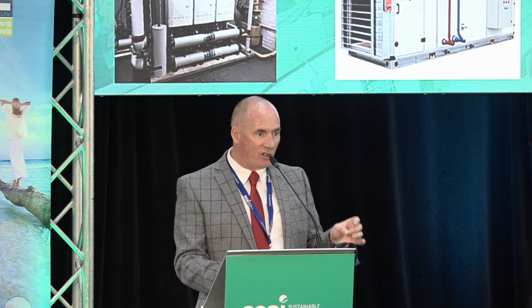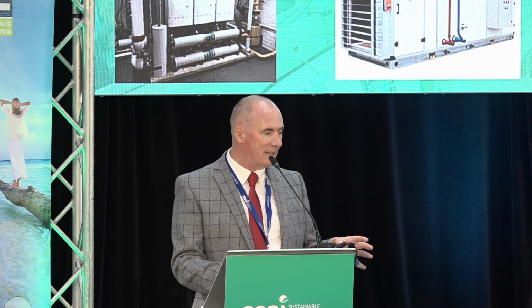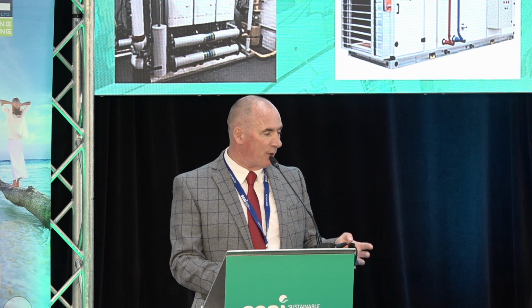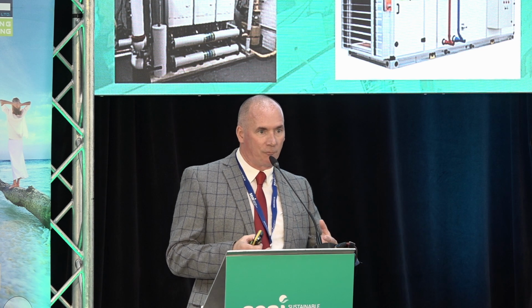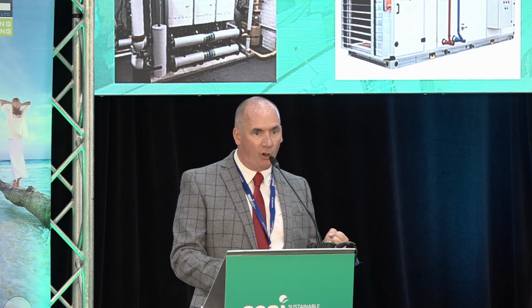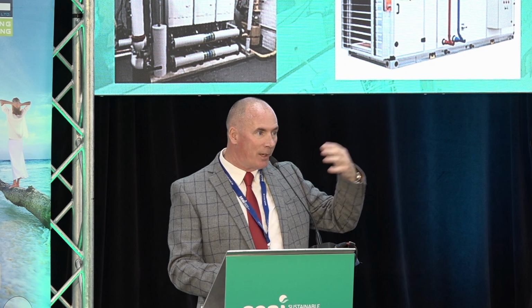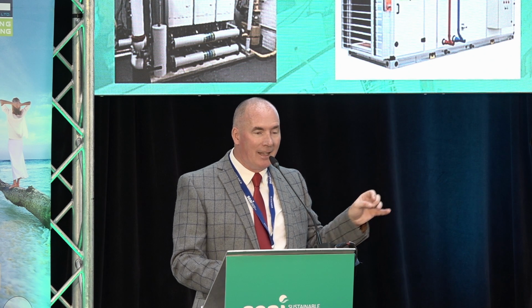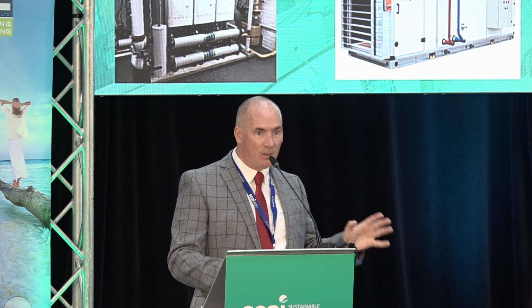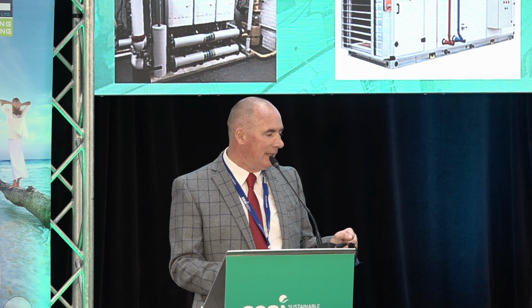So the historical alternative was a water-based system. You would typically have a chiller, a water chiller that provides the cooling, and you would have had a boiler that satisfied the heating. The problem with this, anybody that knows refrigeration and chillers will know that the condenser is basically dumping energy. As we're cooling the water, we're taking energy from it and we're dumping that from the condenser to the environment. And at the exact same time, we could have a boiler running, generating heat. Okay, so you can see where the problem is here. That is the way it was done forever, and actually still is on certain projects you wouldn't believe.